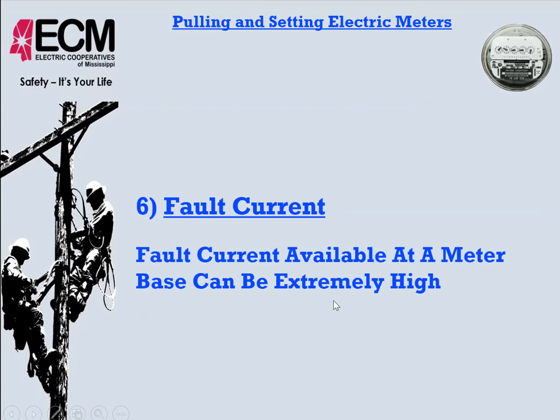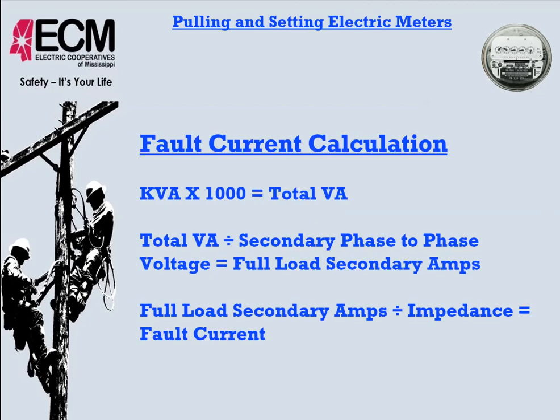Fault current. There again, I think we have a false sense of security in meter bases simply because it's household voltage. Sometimes we take it for granted and think that it's safe. But fault current in a meter base can be extremely high, and fault current and arc flash go hand in hand. I've got some videos in just a second that show us what actually could happen. But we can figure the fault current in a meter base.